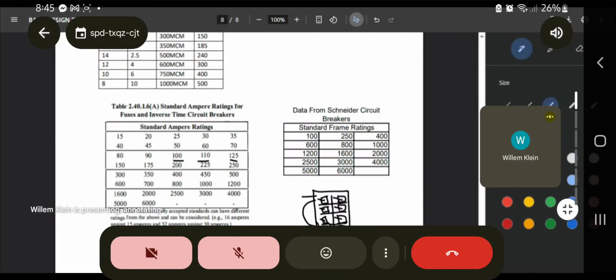So again, you can use a smaller rating. So the next smaller one, because we computed for 95 amperes. So the closest one there is actually 100. But for flexibility, you can use 110 or 125. Okay? So why did they use 125? So usually, in practice or in hardware, if you ask for available circuit breakers, the 125 rating is more available, most of the time, than 110. Okay, so that's why you can also select 125.